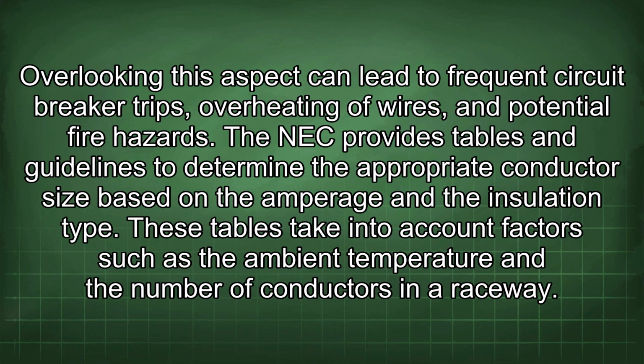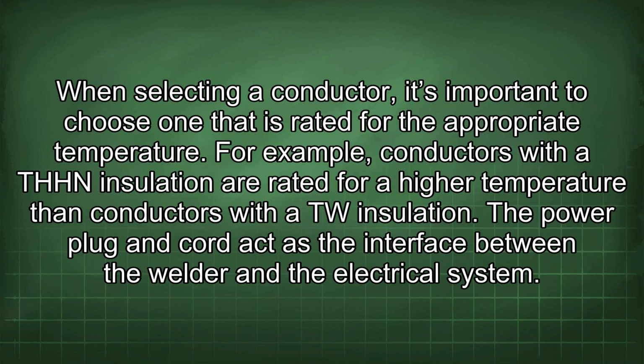These tables take into account factors such as the ambient temperature and the number of conductors in a raceway. When selecting a conductor, it's important to choose one that is rated for the appropriate temperature. For example, conductors with the THHN insulation are rated for a higher temperature than conductors with the TW insulation.